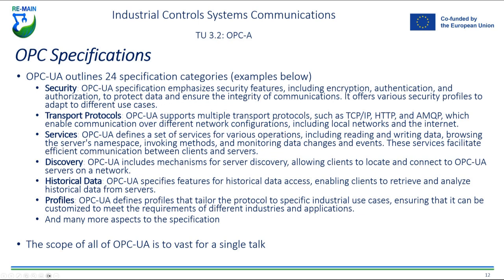OPC UA supports multiple transport protocols such as TCP/IP, HTTP, and AMQP, enabling communication over different network configurations, whether on a local network or routing data externally. The services OPC defines include reading and writing to OPC servers, providing service namespaces, invoking methods, and monitoring data changes and events — facilitating efficient communications between clients and servers. OPC UA also includes a server discovery mechanism, allowing new clients to locate and auto-discover OPC servers on a network. Additionally, it provides specifications for historical data access, which is useful when you need to retrieve data over a period of time.